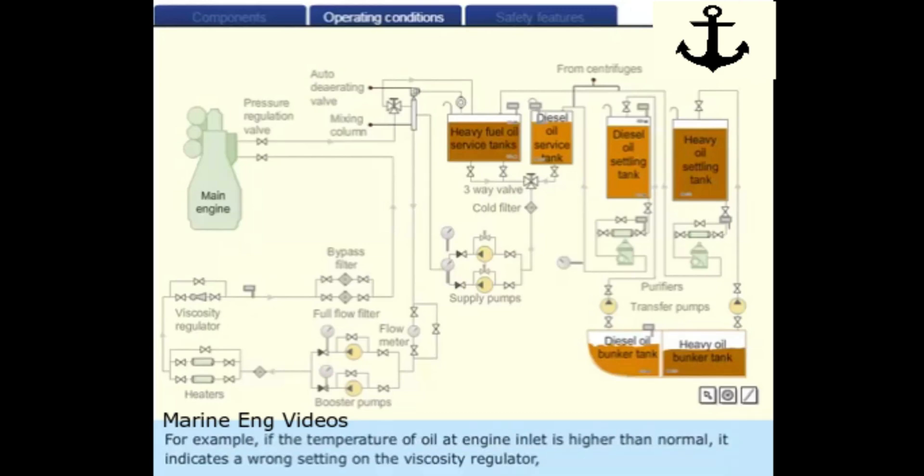For example, if the temperature of the oil at engine inlet is higher than normal, it indicates wrong setting on the viscosity regulator. If the pressure of the oil at the engine inlet is lower than normal, it indicates a clogged filter.